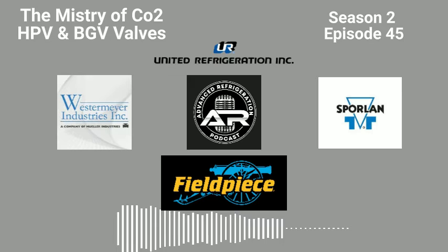But the temp sensor, I've seen it both ways. I've seen it where Danfoss wants it six inches from the T, where the condenser's T and gas cooler T come together, is where they want it. Now, in a perfect world, that's where it should be. But when the rack manufacturer sends all this out pre-done and it's not in the prints, it's where it ends up being. As long as you're insulated good, I don't see much loss of performance. All right. And then the BGV, that pressure transducer is going to be on the flash tank because that's what we're trying to control, right?